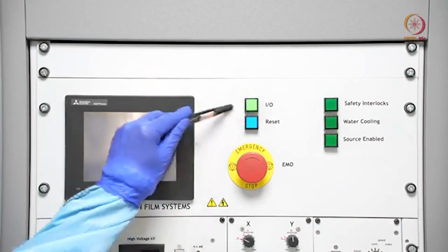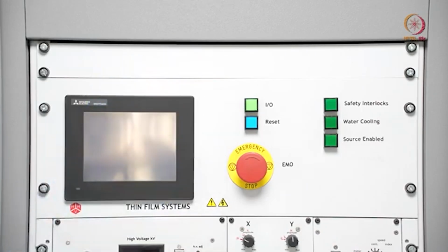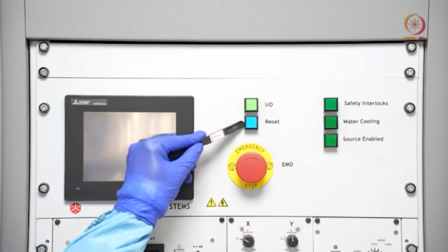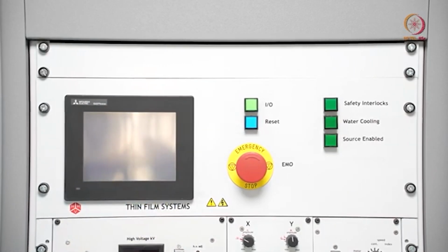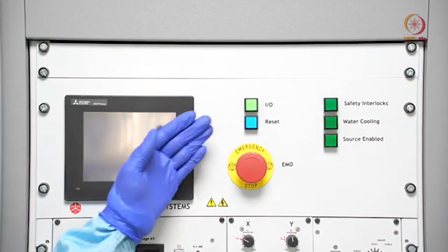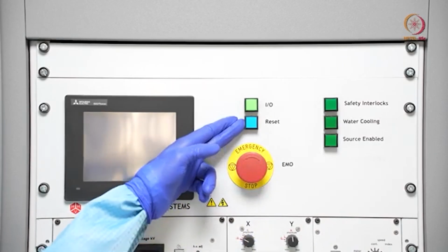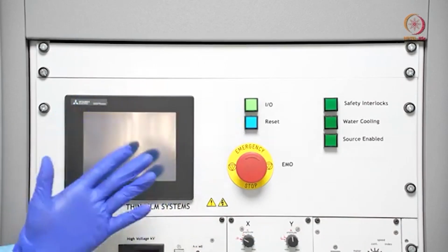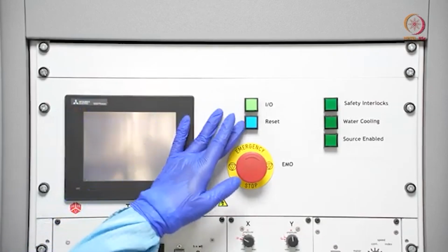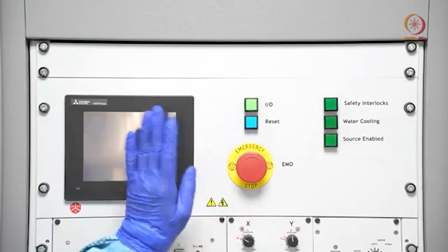So this corresponds to the main supply, or the electrical supply, of this tool. Here is the reset. By any chance, if you switch off the tool in a hurry, or if you press this emergency stop button because of some emergency, or if it is not on properly, there is some trip or some electrical issue, then there will be a hardware reset option.